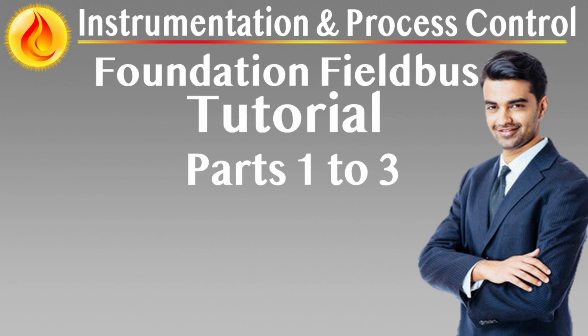Their internal architecture enables them not only to transmit process measurements, but also to execute control logic, report diagnostics, and maintain synchronized operations with the broader automation system. Each Fieldbus device must comply with Foundation Fieldbus function block architecture. At a minimum, all devices shall include the transducer block linking sensor actuator hardware with communication, and at least one input, output, or control function block.